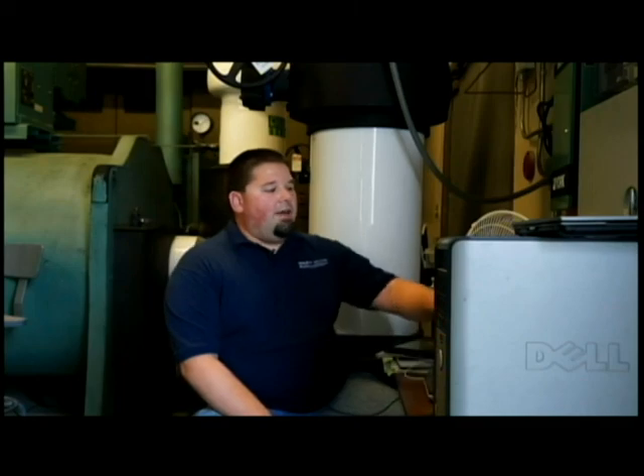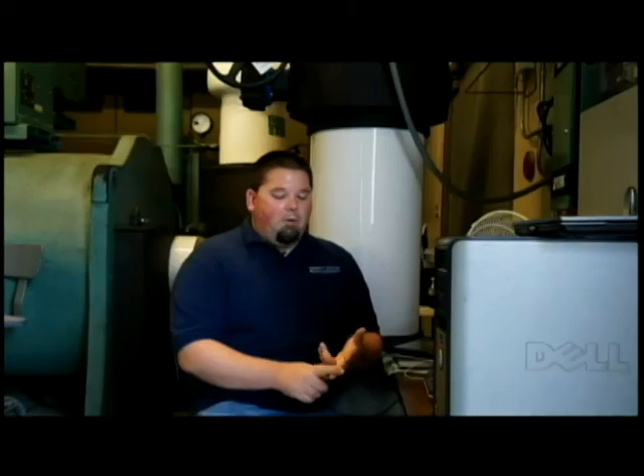When the condenser water pumps run, they also have a lead selection inside of this little box right there, labeled condenser water pumps. Currently, they are set for 2, 3, 1, just like the chillers. That just represents the number of the piece of equipment, and it's going to be lead, lag 1, lag 2. Right now, lead is our condenser water pump 2, and then lag 1 is number 3, lag 2 is number 1.